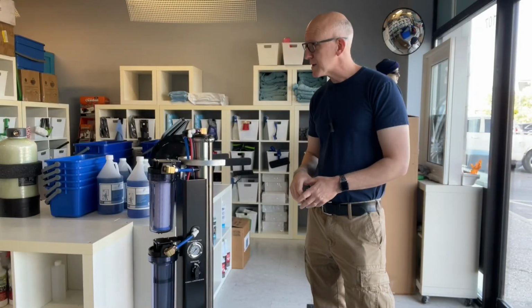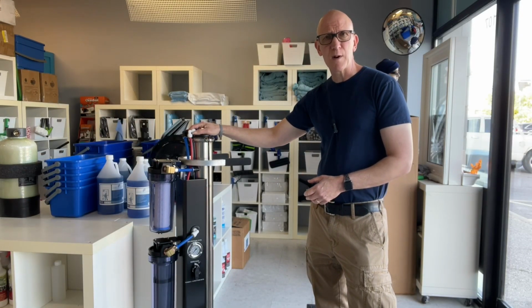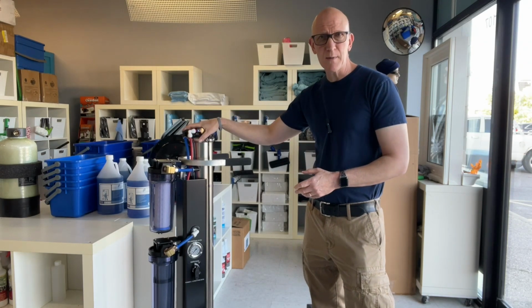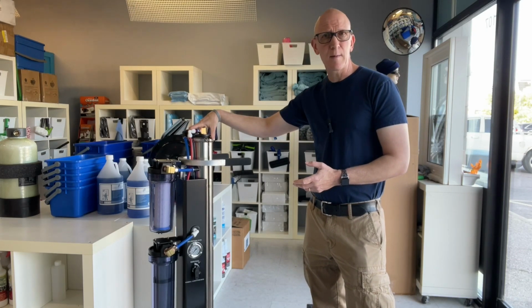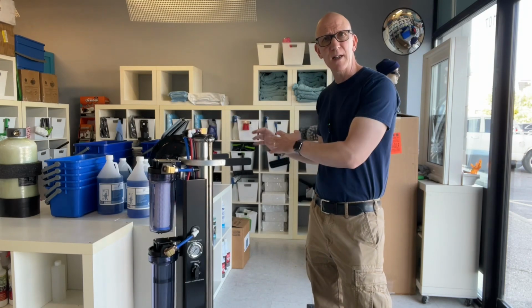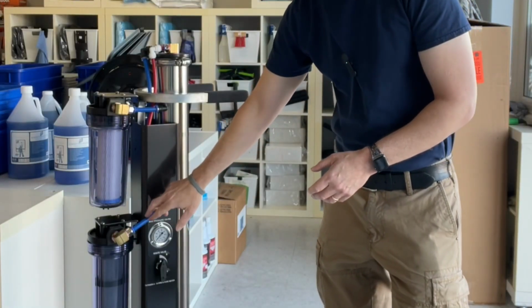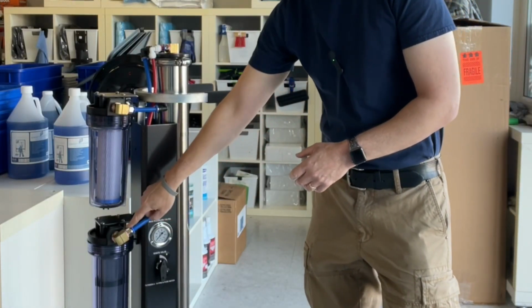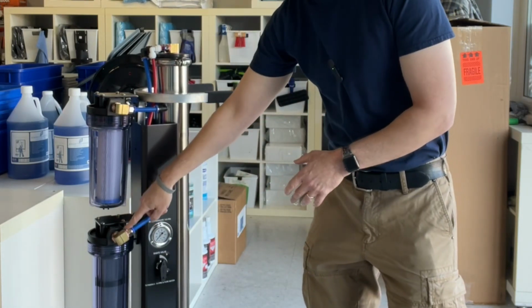So now that brings us to the RO. If there is an actual problem with the RO as far as pressure going through it, a good telltale sign, without even having to open up the system itself, is to check how it's reducing the TDS. A new or fairly new RO membrane should be reducing the incoming TDS by up to about 95%. Now you can test that simply by taking the tube that goes from the output of the RO to the input of the DI.